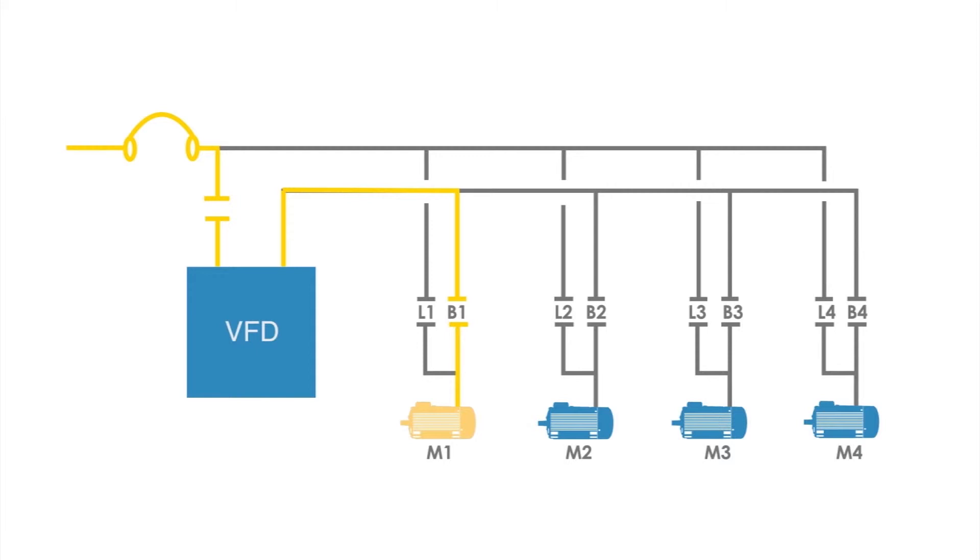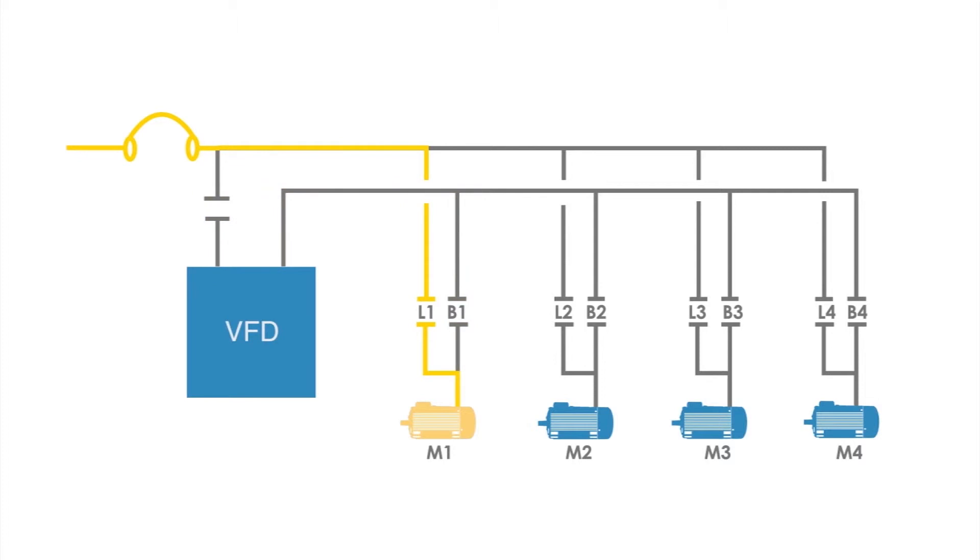If motor M1 driving pump 1 cannot keep up with the process requirements, the VFD is likely operating at full speed. The system synchronizes motor M1 voltage to the incoming line voltage until the voltages are perfectly balanced and in phase. Once that has occurred, contactor L1 is closed and the motor is transferred from VFD operation to the incoming line. This is a closed transition or bumpless transfer.